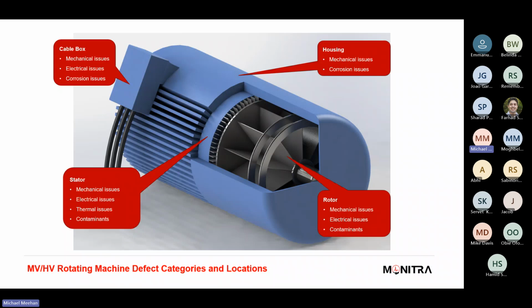differences in temperature. If the cable box itself is sealed, especially if there's a seal break between the stator housing and the cable box, you can get the heat from the machine going into the cable box. And maybe the machine then is switched off, and then you get these big temperature swings in the cable box, and you can end up with moisture in the cable box, which then leads to surface tracking. And I've seen quite a few cable failures in the Pilbara in transformer and cable boxes because of surface tracking and issues. So it is certainly a consideration when you are looking at your asset management plans for a HV machine, is how is that cable termination managed, and certainly make sure that you've got some visibility or some plans in place to make sure that it remains in a healthy state.